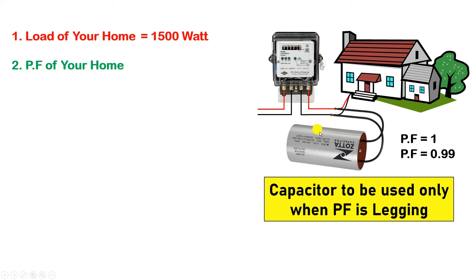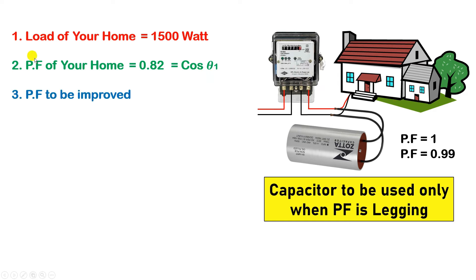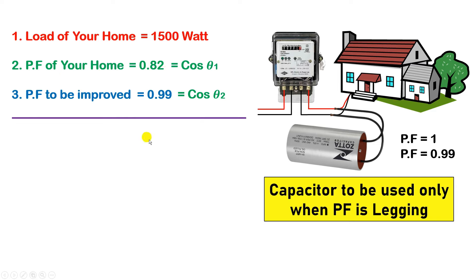For example, suppose our home has 1500 watt (1.5 kW) load connected. Second, what is the current power factor — suppose it is 0.82, which is lagging, denoted as cos theta 1. Third, how much do we want to improve the power factor — suppose we want it to be 0.99, denoted as cos theta 2. Now we need to find theta 1 and theta 2.